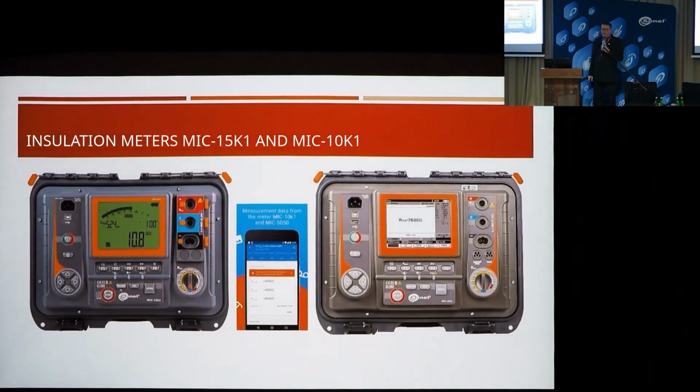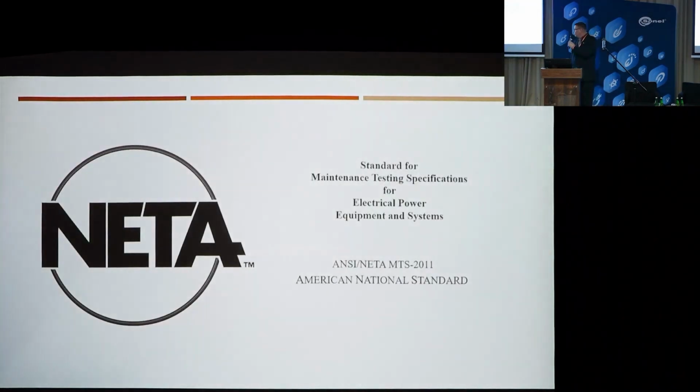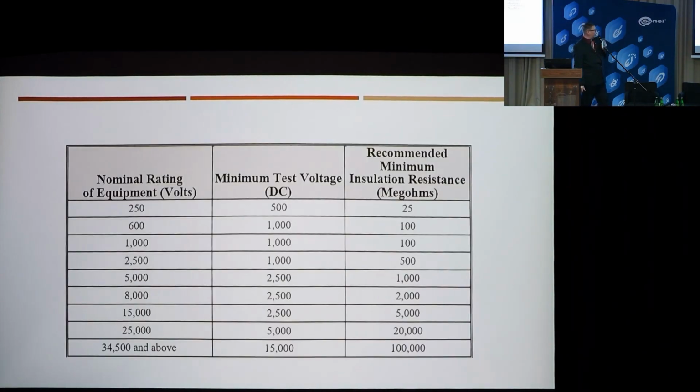And now, why was this whole introduction of mine about the test voltage? Well, ladies and gentlemen, it's because we have 2 meters here that offer a test voltage of 15 kilovolts or 10 kilovolts. And someone will say, but I'll never use that, I'll never need those 15 kilovolts. And where is that even used? Where are voltages like that used? Just to explain, here's the American NETA standard, which shows where those 15 kilovolts are used.